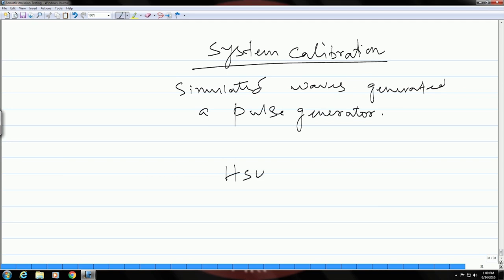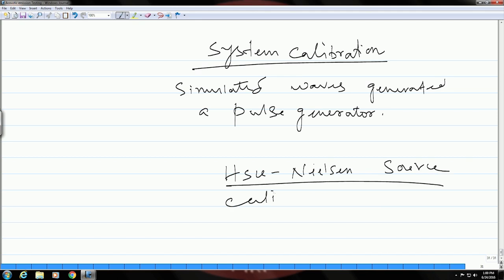In order to overcome this limitation, these two persons came up with a method or source which is very close to an actual acoustic emission source. This source or method is named after the inventors Hsu and Nielsen, and is known as the Hsu-Nielsen method or Hsu-Nielsen source to calibrate acoustic emission systems.